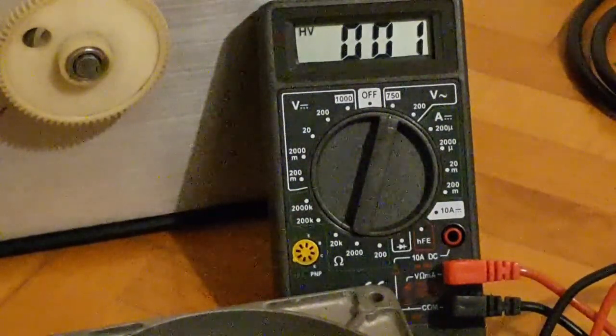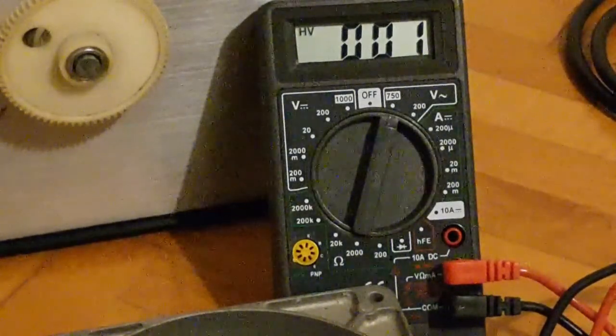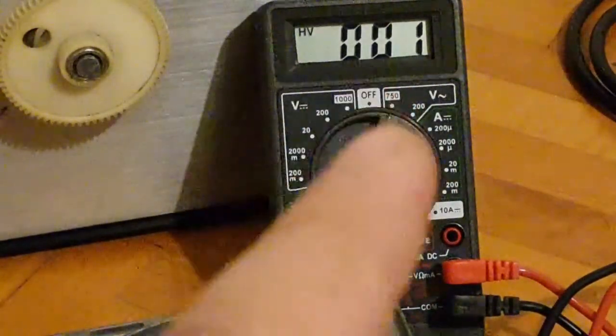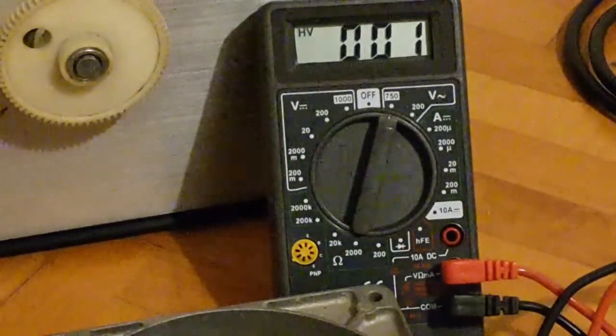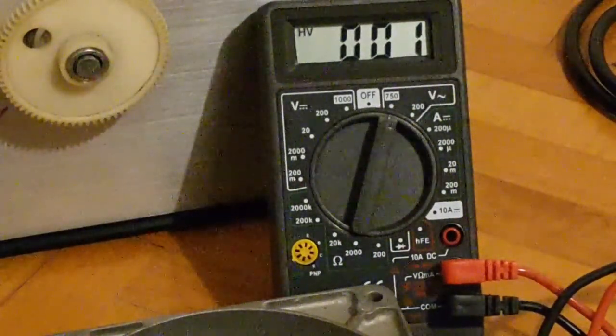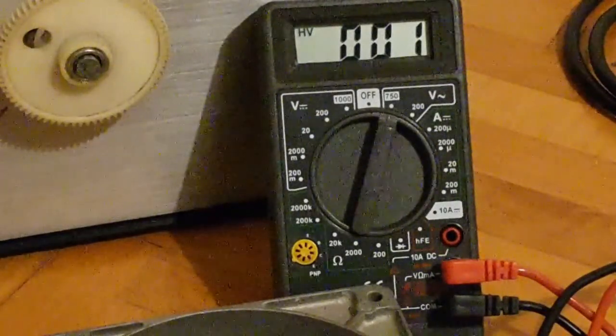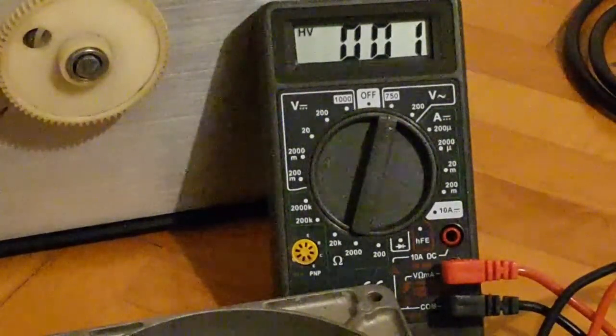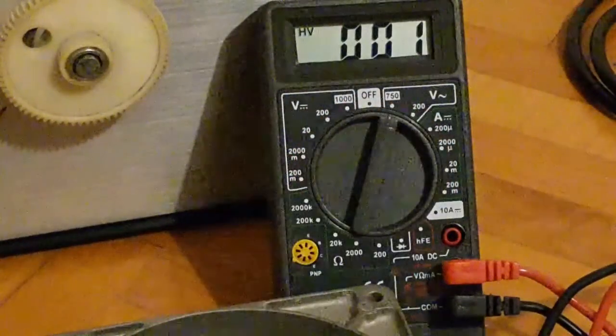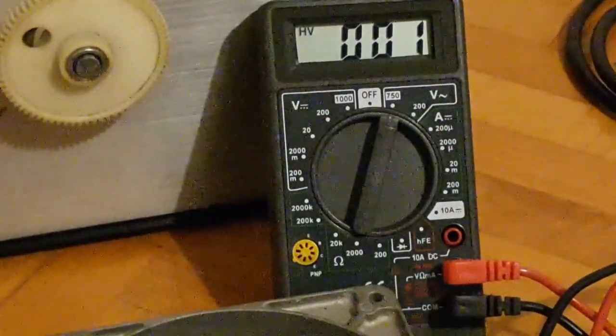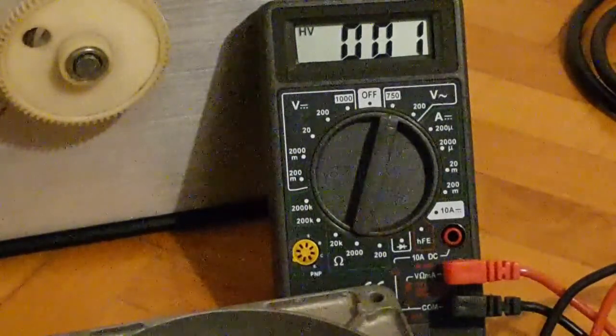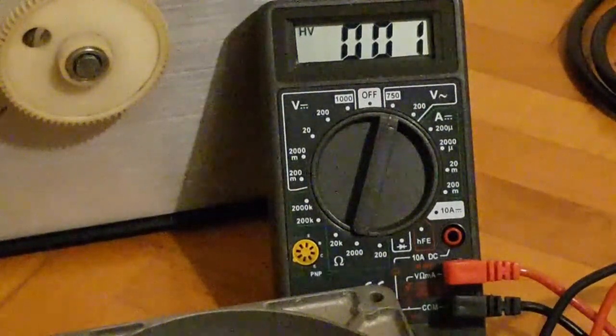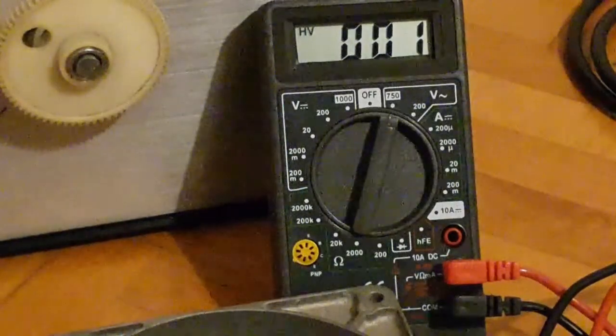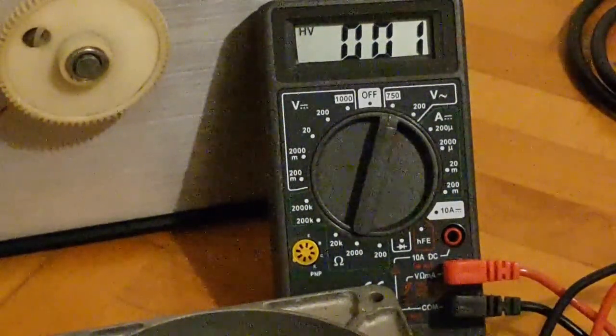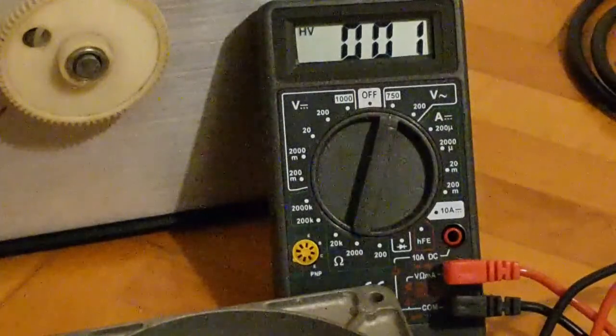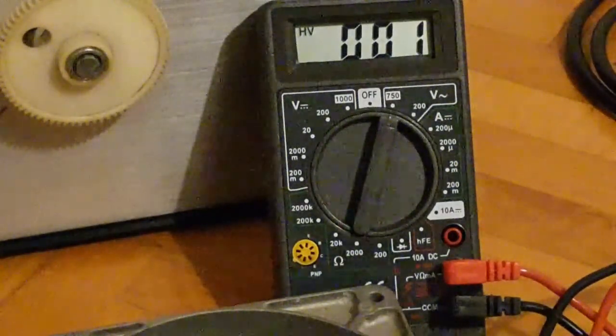What's also really important is that I have the multimeter set to the correct scale or measuring range for AC voltage, because this fan requires between 200 and 240 volts to be powered, so the scale has to be higher than 200 volts so I won't burn up anything on the multimeter.